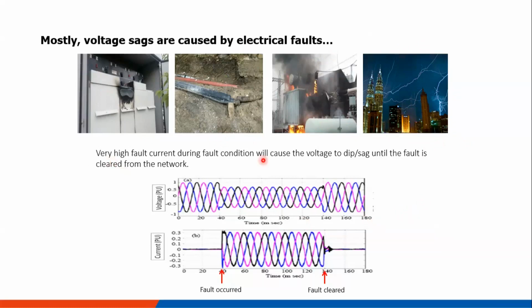So, how long does this voltage sag last? The voltage sag lasts until the fault is cleared. As you can see here, this is the current during the event. Starting from when the fault occurred, we have a very high current. When we have a very high current, the voltage drops significantly. And then the voltage is reduced, from here to here, for as long as the fault lasts, until the fault is cleared. So this will be the duration of the voltage sag. The voltage will be below the nominal voltage until the fault is cleared. So we understand that voltage sags are mostly caused by electrical faults.